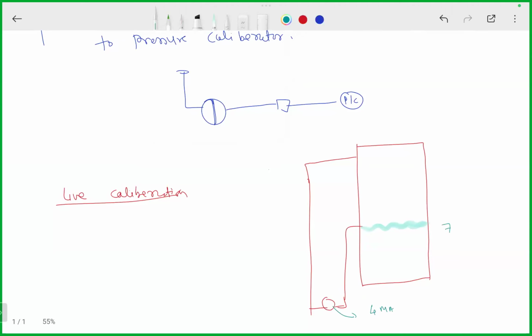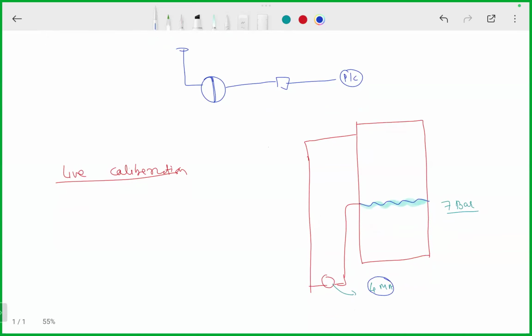You are going to keep the pressure at 7 bar and you are going to bring the level to low water level. DP transmitter should produce 4 milliamp signal. If it is not producing, adjust by zero setting. Then you are going to raise the level to high water level, DP transmitter should produce 20 milliamp signal.